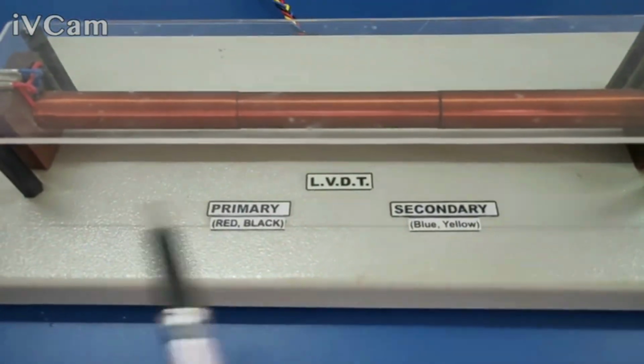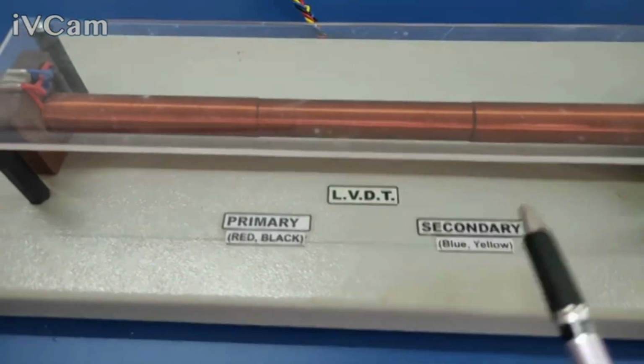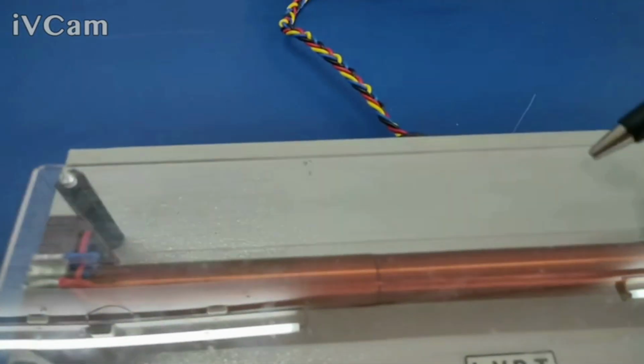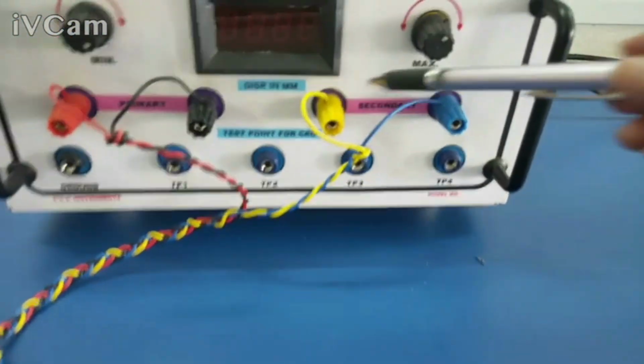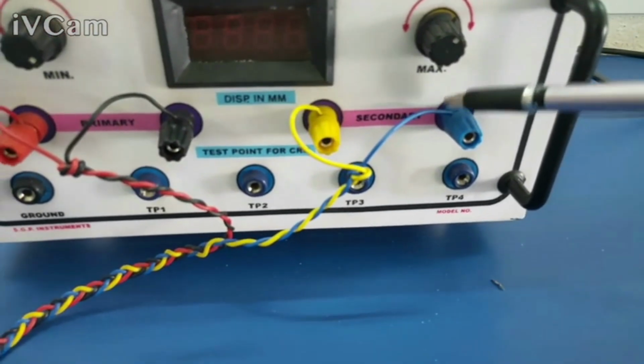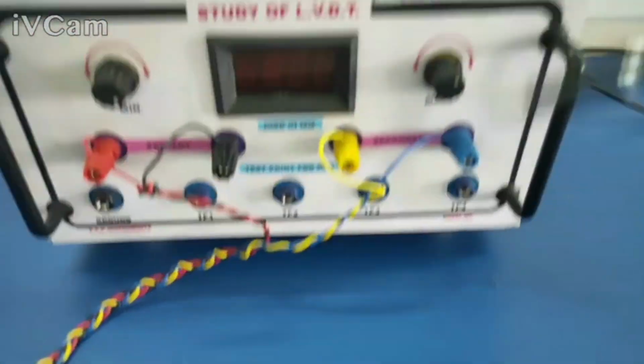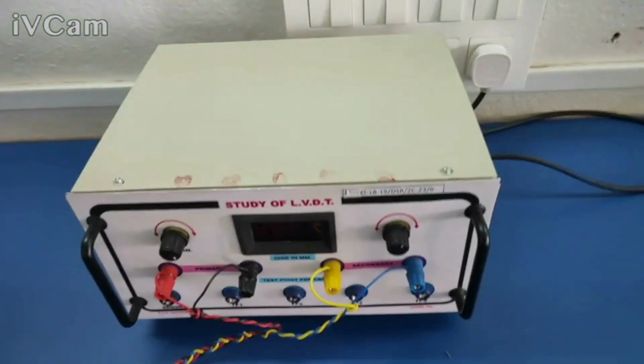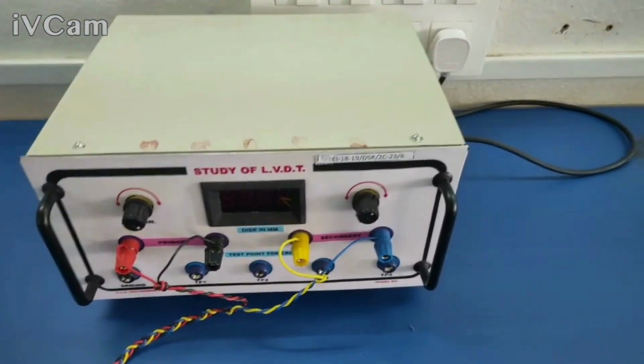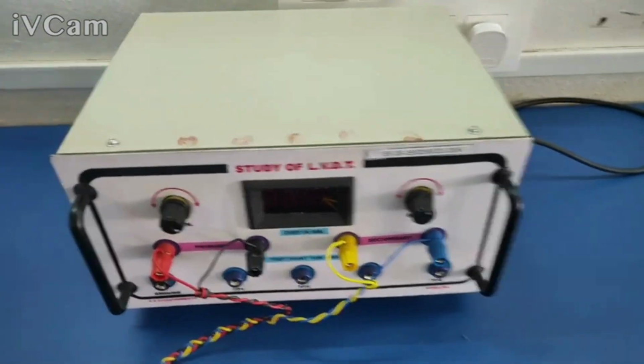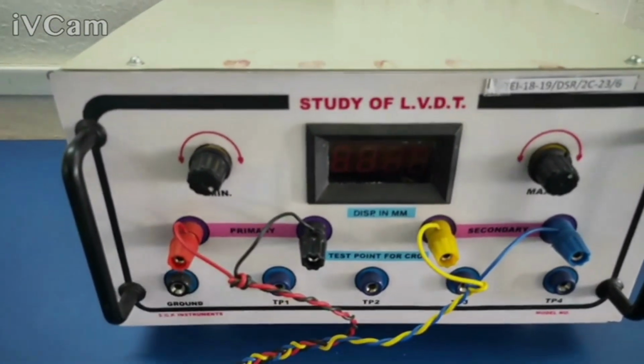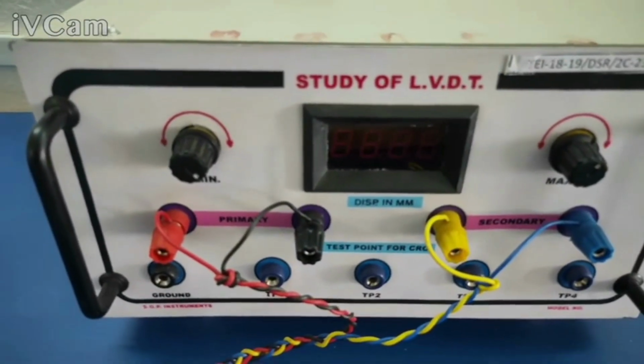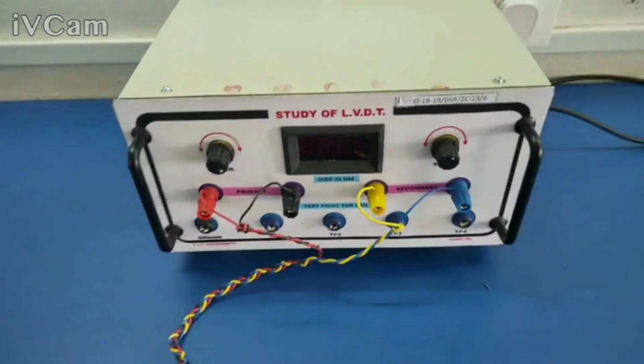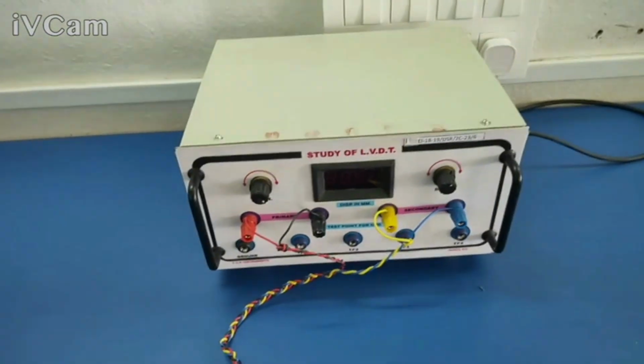Now after the series opposition connection, whatever secondary winding output we get is given back through the cables, a yellow wire and a blue wire, to these two terminals, where we get the variable secondary voltage. This variable secondary voltage is then fed inside to the A to D converter, which converts it into digital form, and that EMF in digital form is displayed on this panel, which is nothing but millimeters of displacement. Now let us study how this meter is going to work.